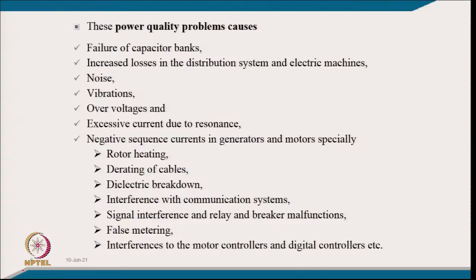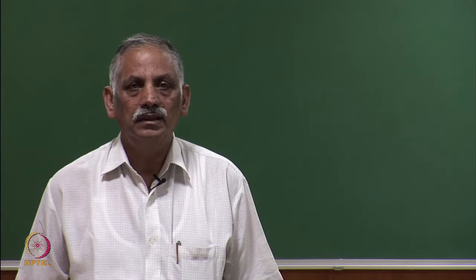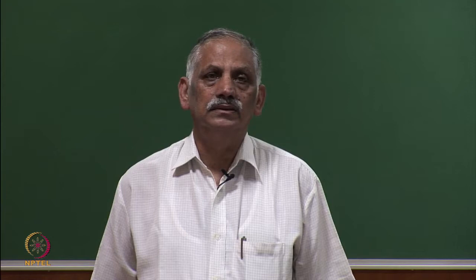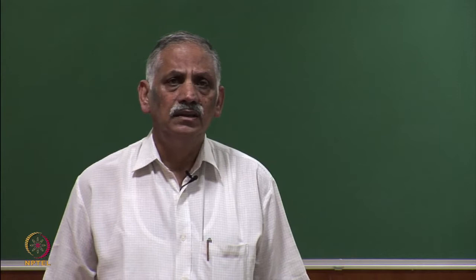Power quality problems also cause negative sequence current in generators and motors, especially causing rotor heating. For example, in an induction motor, 1 percent negative sequence voltage — or 1 percent unbalance — results in 5 to 6 percent negative sequence current. So even a balanced induction motor amplifies negative sequence current by around 5 to 7 times.